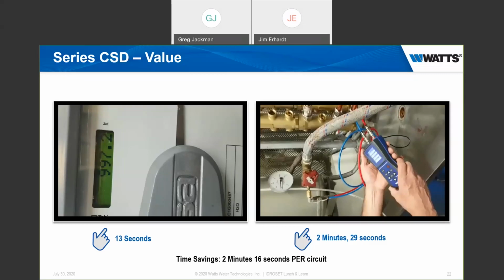And it goes down lower than most other valves, and that has to do with the construction of the valve and the way the flow meter was constructed inside the valve. And the upper end of the flow rates are pretty much what you would expect. So that goes to that expanded window we were talking about, in terms of being able to operate over a broader band of flow rates.